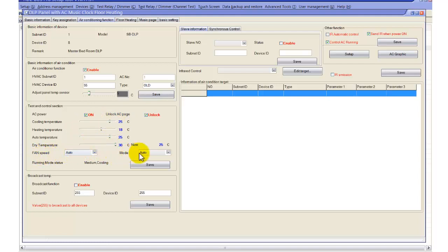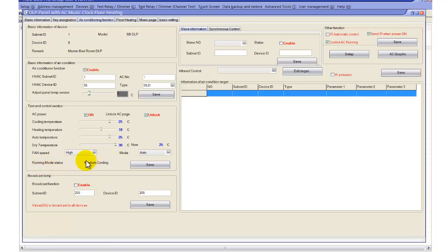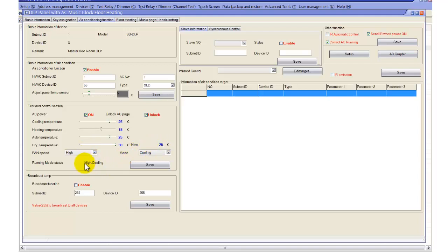We have fan speed and mode options, and we can test the module. The running mode status now shows medium speed, cool mode. I can also change it to cool with high speed — when I save, it changes to high cool. This lets you double-check that you are connected to the right HVAC module. You can also see the actual room temperature, which is 25 degrees.